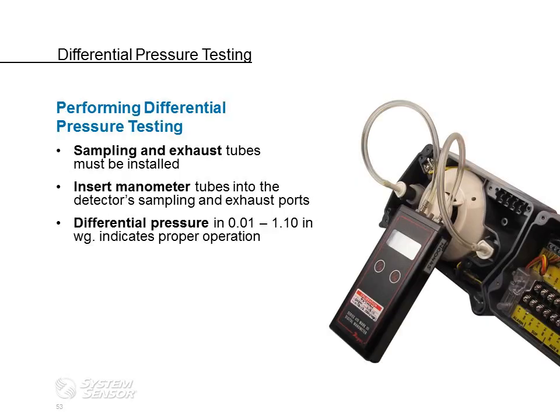The way you perform that pressure differential test is remove the cover. You'll see the plugs on the end of the tubes. Those plug into the sampling tube and the exhaust tube. Insert the manometer tubes. You'll get the reading, and what you're looking for is a differential pressure. It has to be between 0.01 and 1.10 inches of water. As long as you're between those two limits, that ensures that you're getting proper airflow, that you're drawing a proper air sample across the smoke detector head.